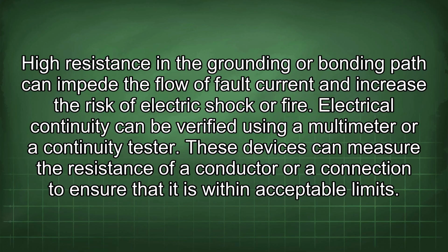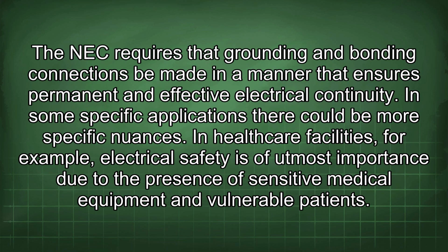Electrical continuity can be verified using a multimeter or a continuity tester. These devices can measure the resistance of a conductor or a connection to ensure that it is within acceptable limits. The NEC requires that grounding and bonding connections be made in a manner that ensures permanent and effective electrical continuity. In some specific applications, there could be more specific nuances.